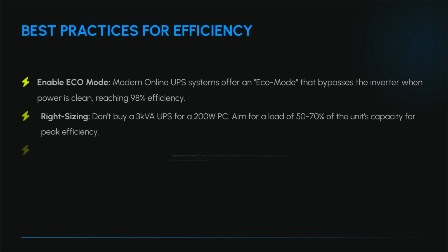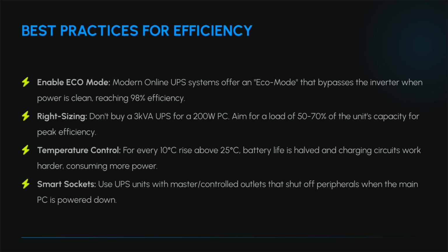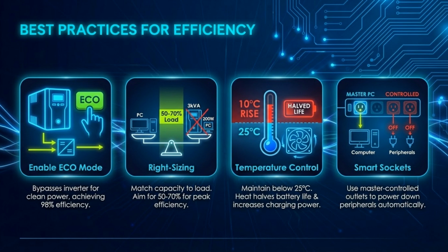Best practices for efficiency include enabling eco mode for higher efficiency and right-sizing your unit for a 50 to 70% load. Control temperature below 25 degrees Celsius and use smart sockets to shut off peripherals. Implementing these practices can significantly reduce your UPS's energy footprint and prolong battery life.